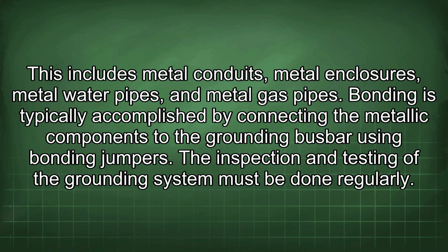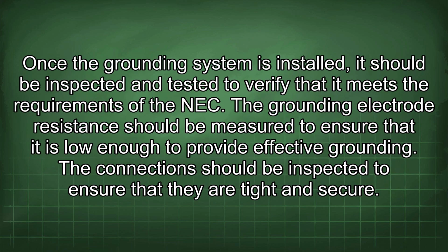Bonding is typically accomplished by connecting the metallic components to the grounding busbar using bonding jumpers. The inspection and testing of the grounding system must be done regularly. Once the grounding system is installed, it should be inspected and tested to verify that it meets the requirements of the NEC. The grounding electrode resistance should be measured to ensure that it is low enough to provide effective grounding.